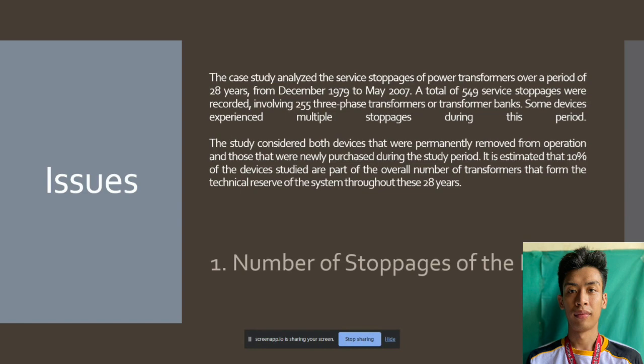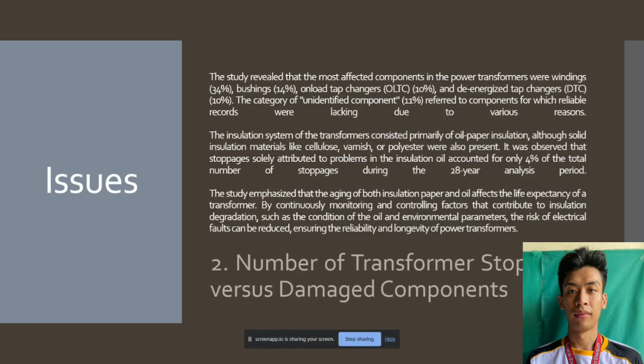The study considered both devices that were permanently removed from operation and those that were newly purchased during the study period. It is estimated that 10% of the devices studied are part of the overall number of transformers that form the technical reserve of the system throughout these 28 years. The study revealed that the most affected components in power transformers were windings, 34%, bushings, 14%, on-load tap changers, OLTC, 10%, and the de-energized tap changers, DTC, 10%. The category of unidentified component, 11%, referred to components for which reliable records were lacking due to various reasons.